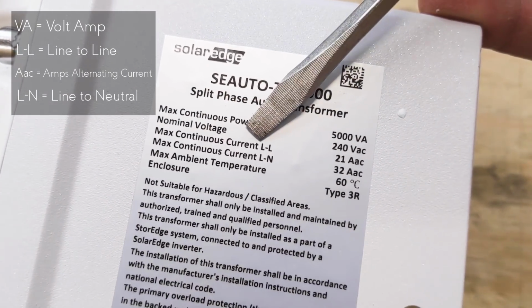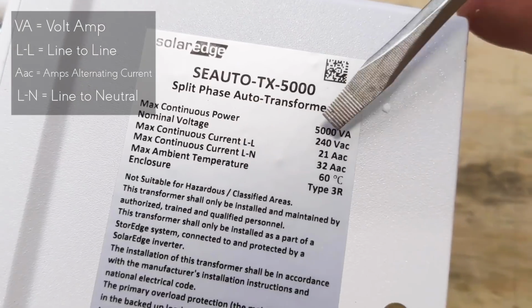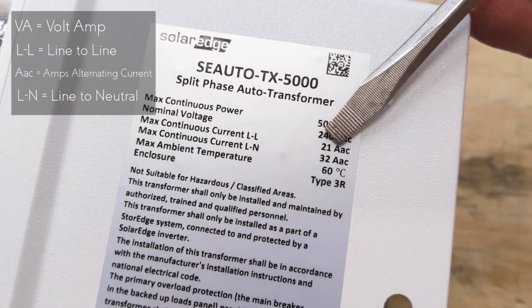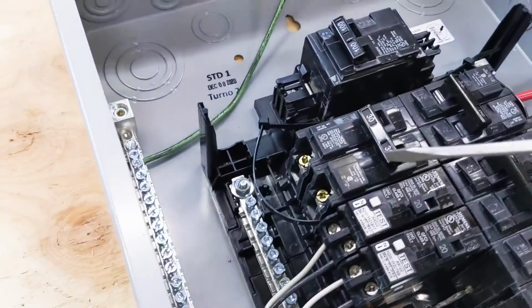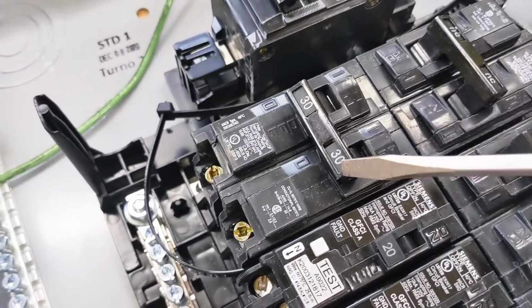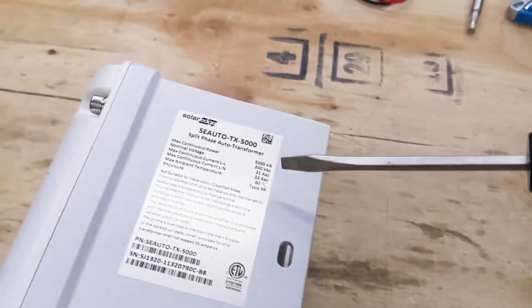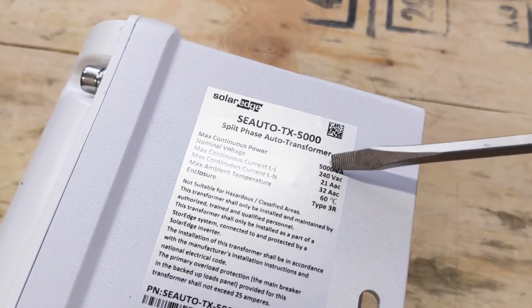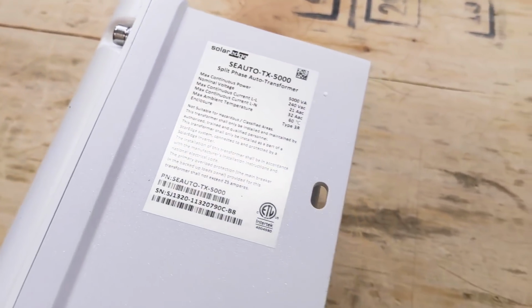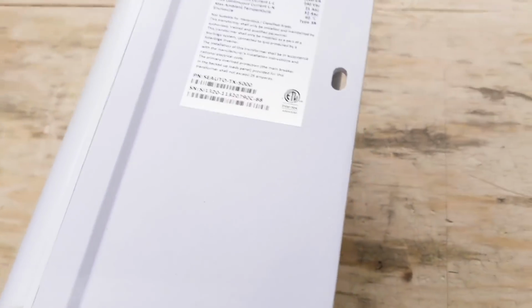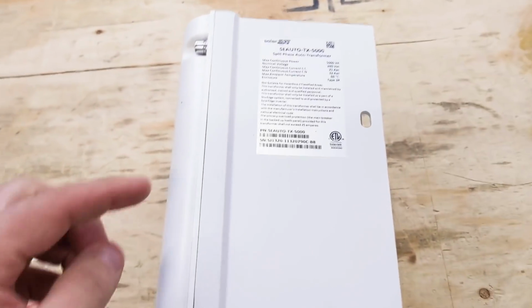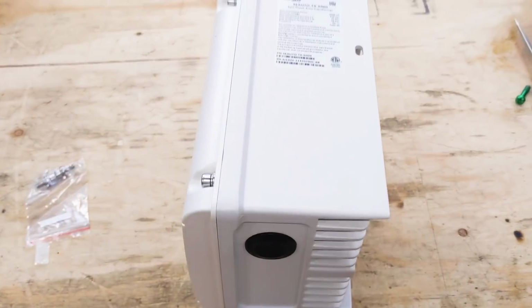So it says maximum continuous current line to line is 21 amps. I'm going to be putting this on a 30 amp breaker right now and connecting it with 10 gauge wire, but I might have to see if I can find a 21 amp, or I might have to put it on a 20 amp. If you guys know the answer, let me know in the comments below.